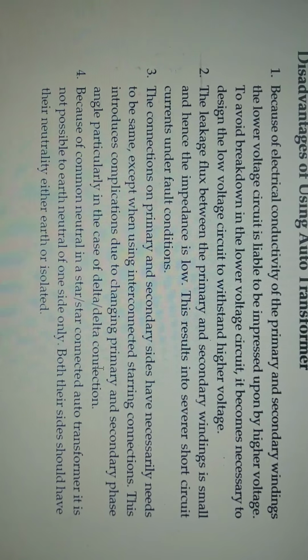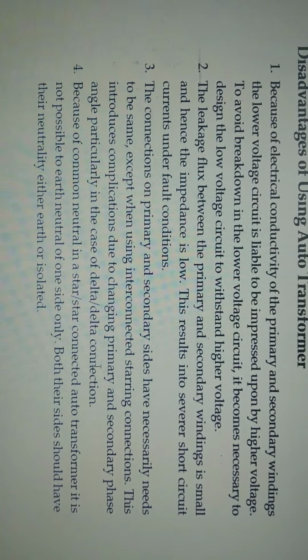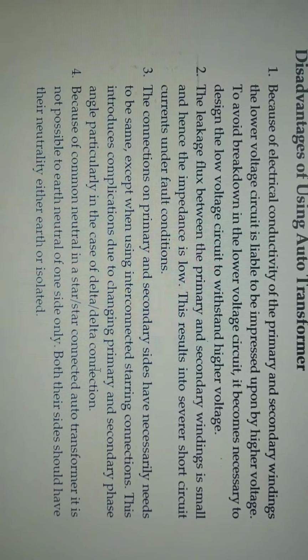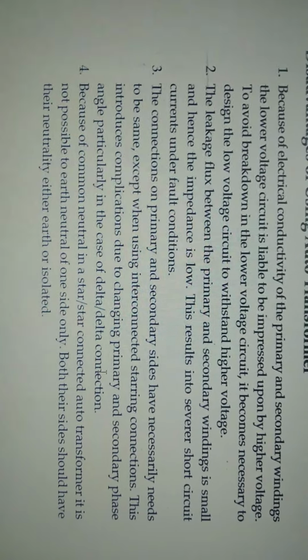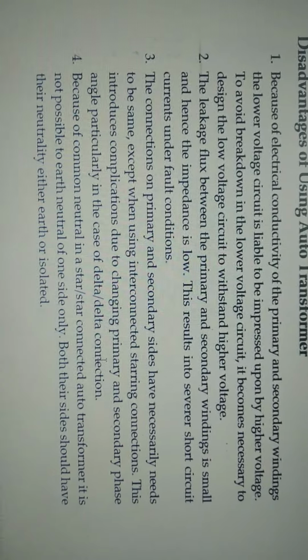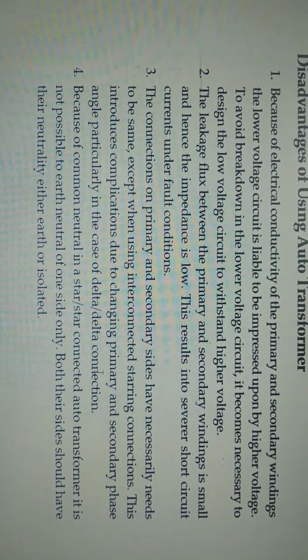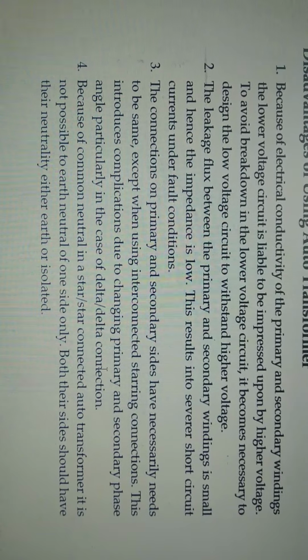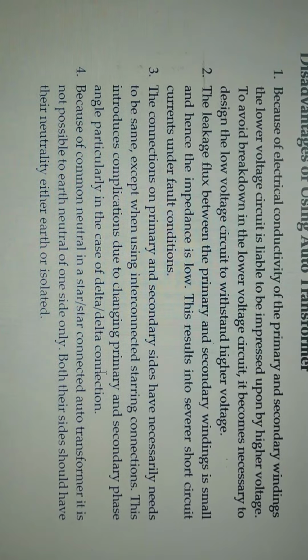To avoid breakdown in the lower voltage circuit, it is necessary to design the lower voltage circuit to withstand the higher voltage values. The leakage flux between the primary and secondary winding is small, hence the impedance is very low. This results in severe short circuit currents under any fault condition.